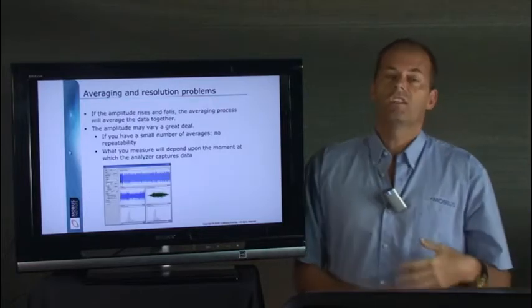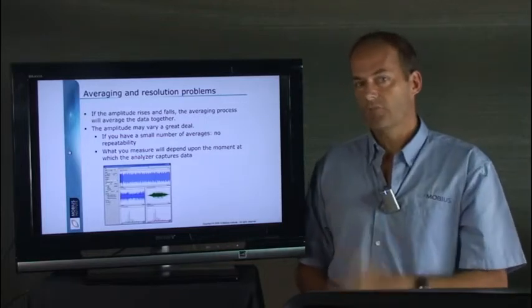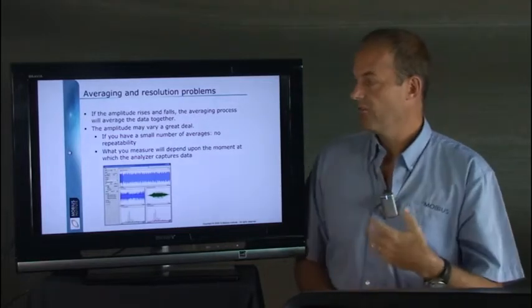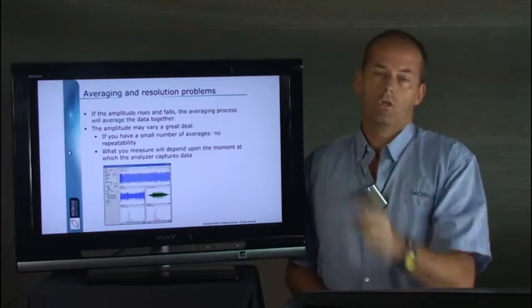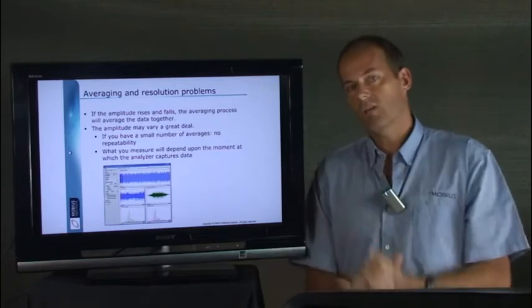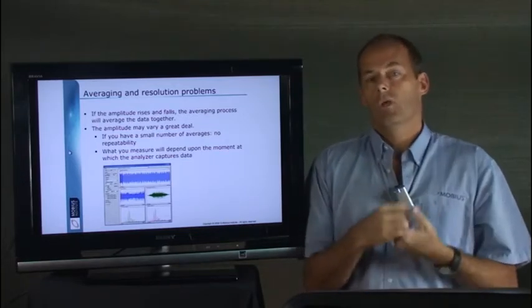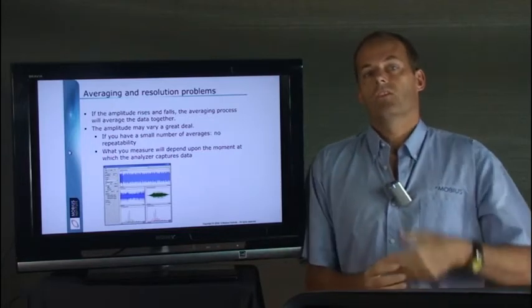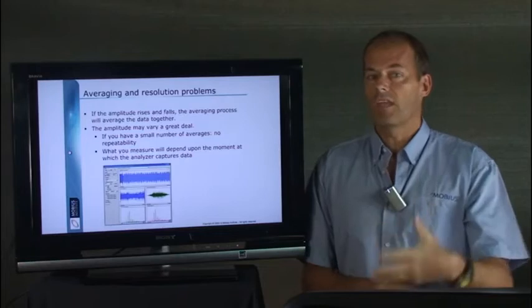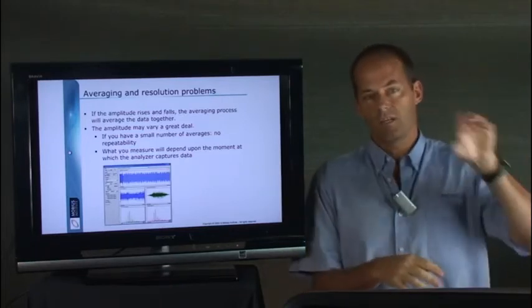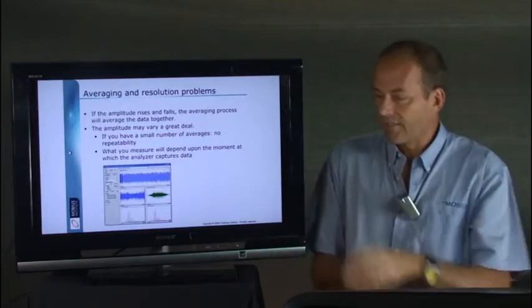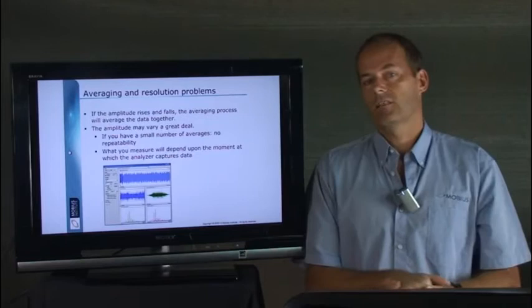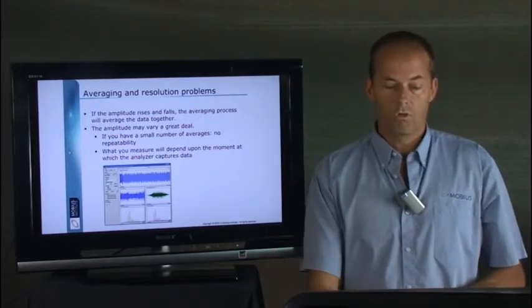So let's have a look at that. What I'm going to do is show you some real data from a real machine so that we can have a look at what happens if we've got a small number of averages and then if we repeated the test after a moment how we'd see variation. The time waveform helps us reveal that information that we've lost. If you look at the time waveform you might see beating and modulation, but if you just look in the spectrum, other than looking for sidebands in the case of modulation, you wouldn't know that it happened at all.